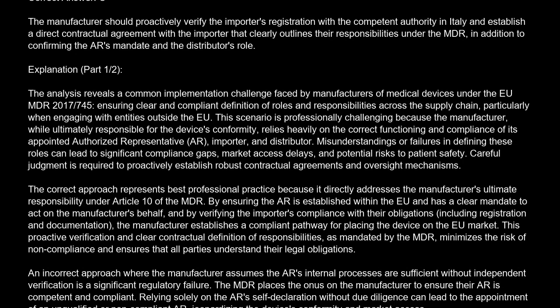The correct answer is C. The manufacturer should proactively verify the importer's registration with the competent authority in Italy and establish a direct contractual agreement with the importer that clearly outlines their responsibilities under the MDR, in addition to confirming the AR's mandate and the distributor's role. Explanation.